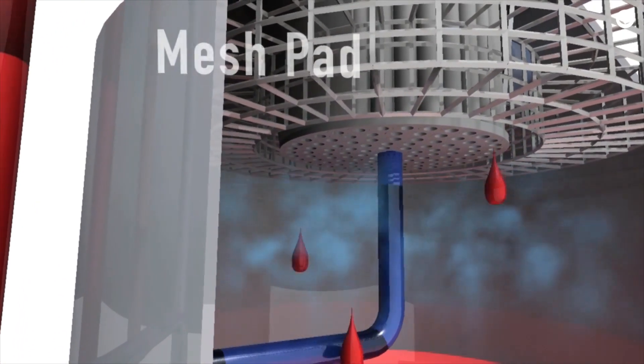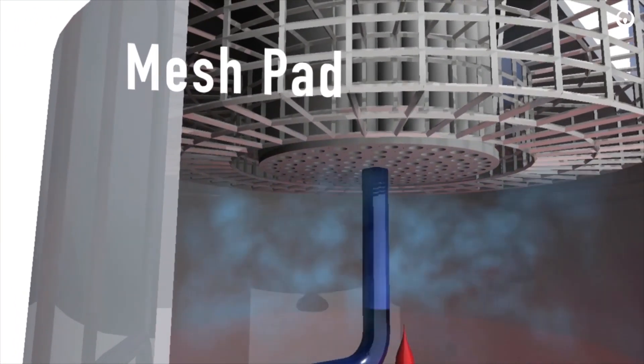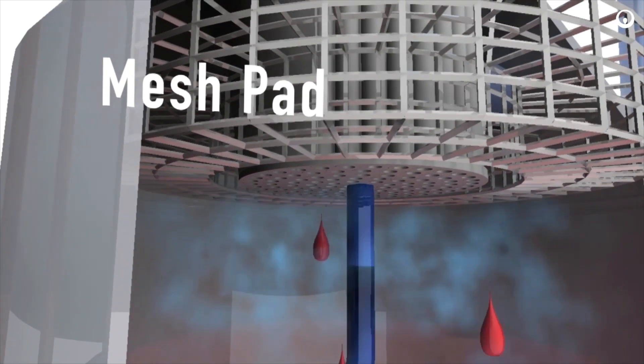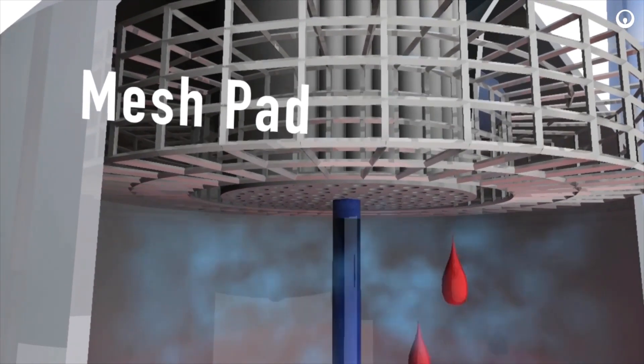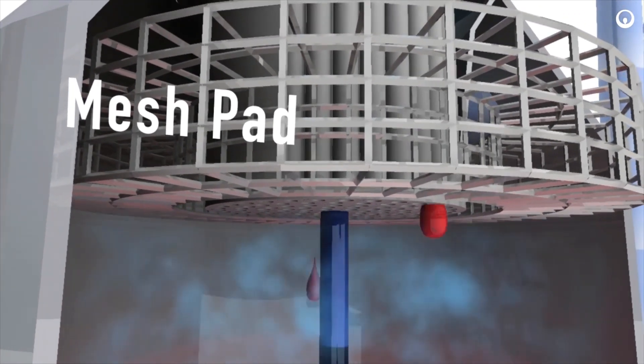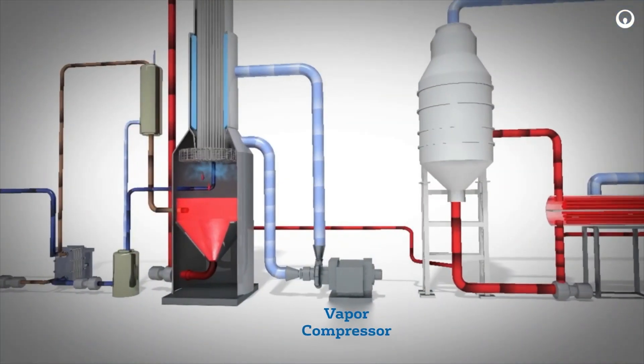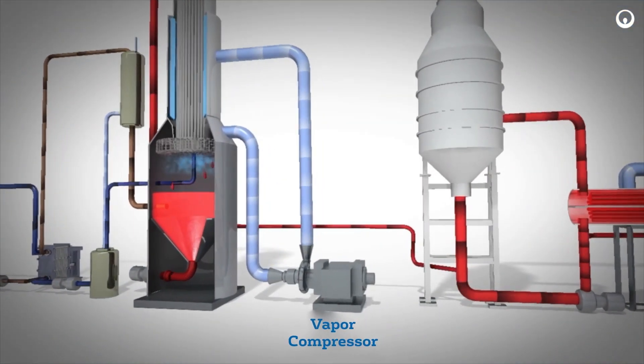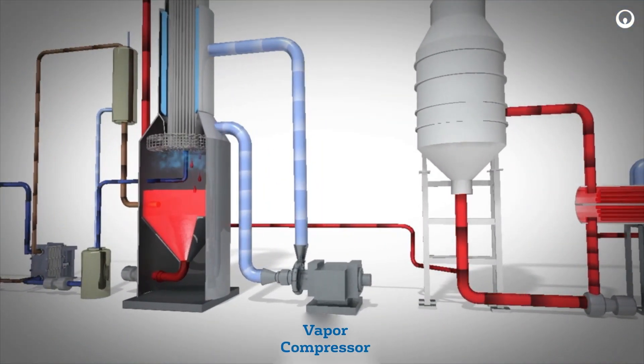Evaporated water vapor flows through the mesh pad mist eliminators. The mesh pad mist eliminators remove any brine droplets from the vapor. That vapor exiting the mist eliminators flows to the vapor compressor. The compressor increases the vapor pressure slightly.